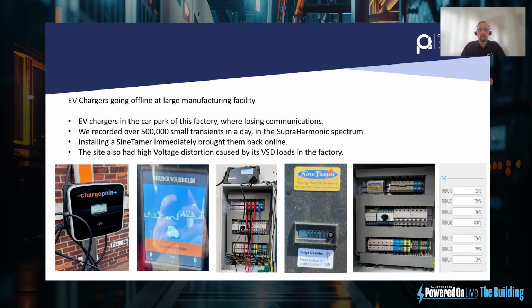If we move on to another example, these are small chargers in the car park for a facility. In that facility, I forget how many chargers there were, but I think it was about 12 or 15 in total in different banks. And two things were happening. One was the chargers were going offline due to a comms loss, and some equipment in the factory was not so happy. And we measured with the PQBox 300 the harmonic spectrum, so we can understand it was actually supraharmonics. And we noticed we had about 500,000 small little transients or high frequency noises that you can see there on the counter in the middle.